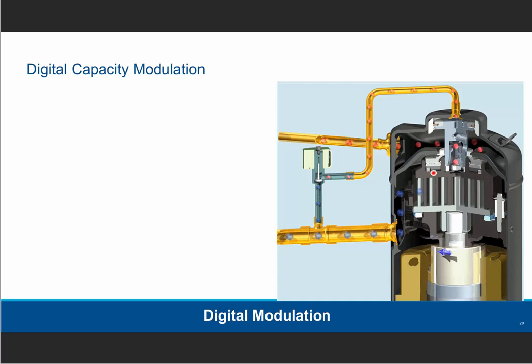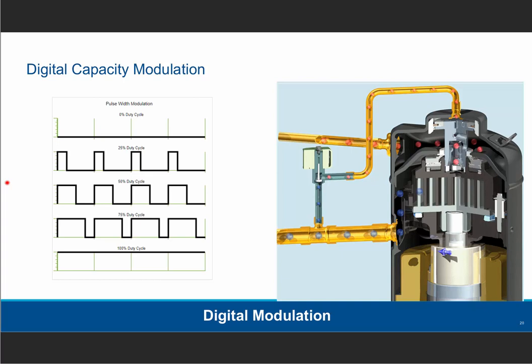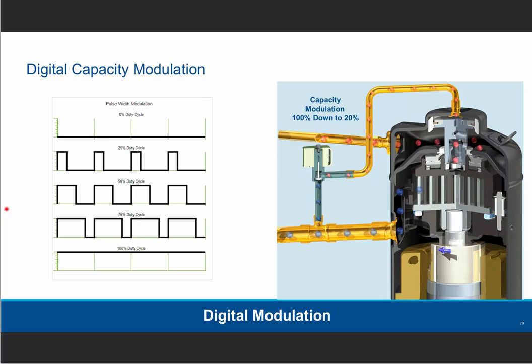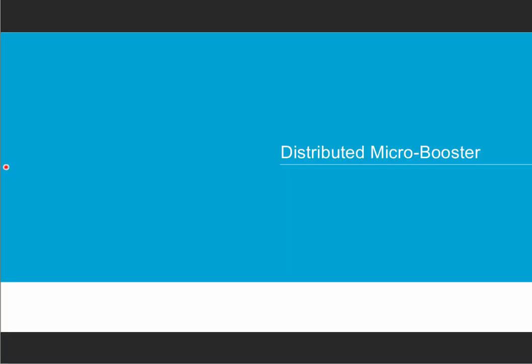100% mass flow. When you energize this little solenoid valve and release the pressure on top of the piston, it moves up with discharge pressure helping to assist it, pushes up, and then you have about a 1 millimeter gap between the orbiting scroll and the fixed scroll, and compression stops. So the actual mass flow coming out of that compressor stops, but the inertia continues to move refrigerant throughout. And it works on a pulse width modulated cycle, typically 20 seconds. So if I'm completely 100% duty, it's on all the time. But if I have 75% duty, that solenoid will be energized 75% of that 20 seconds and then off for that 25%. And that's really how it runs. And that's pretty much the orientation and the functioning of the digital.